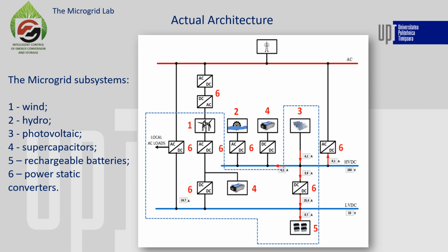So now, this is the configuration of the microgrid lab in a more detailed diagram. The power supply unit, PV panels, and hydro are connected to the 400 volts high voltage DC bus. Actually, the voltage level is around 350 volts due to the direct connection of the PV panels, the value for which the PV panels operate around the maximum power point. Of course, this direct connection was done to eliminate a power converter.